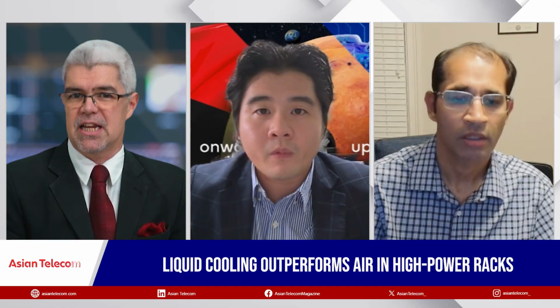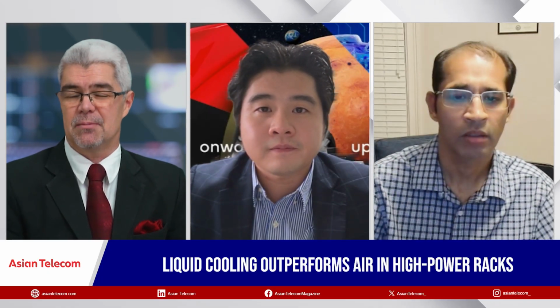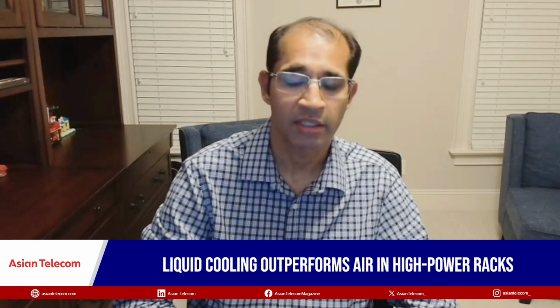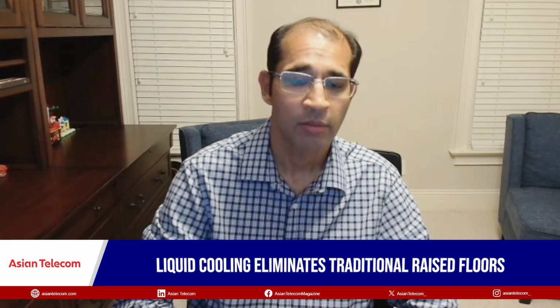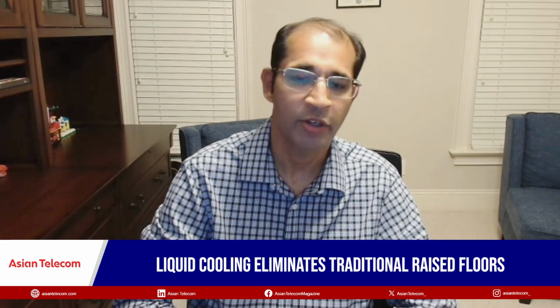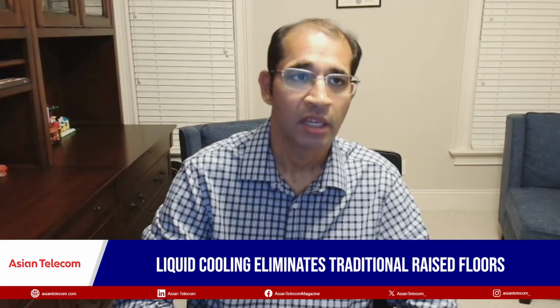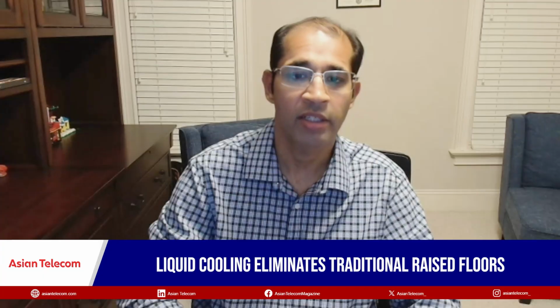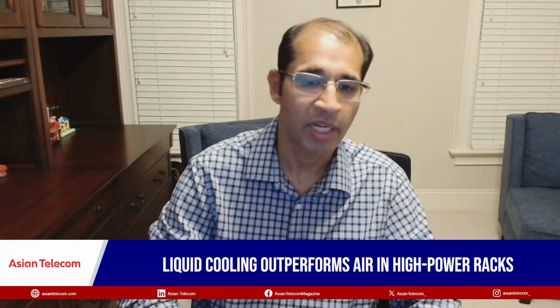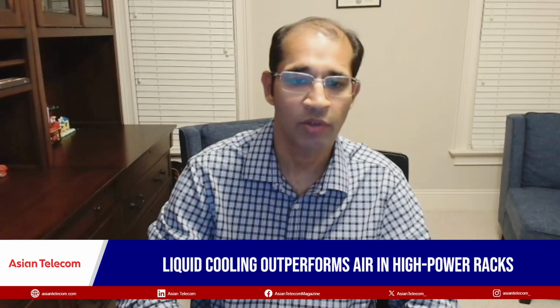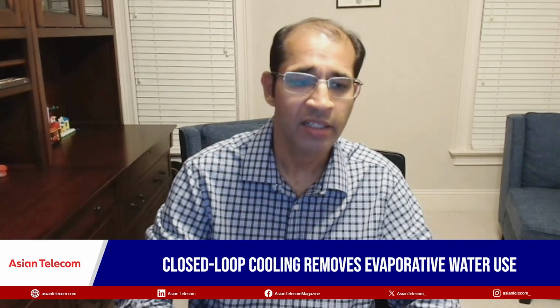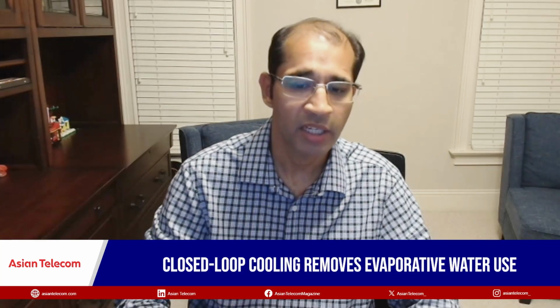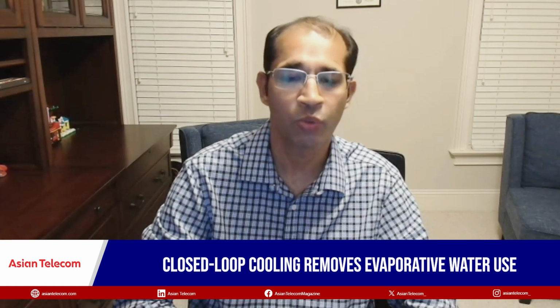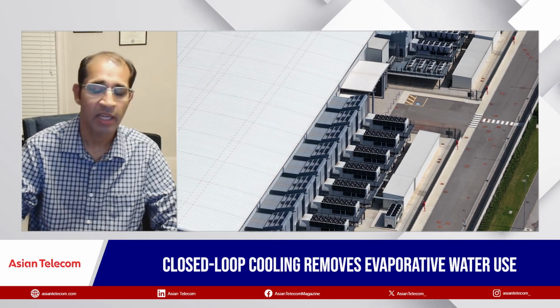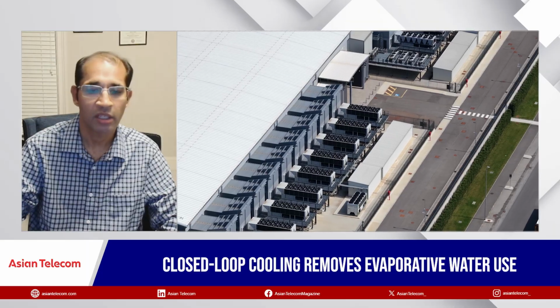What changes will we see in data center design as liquid cooling becomes mainstream? It's a completely new way of looking at data centers. You won't require raised floors any longer, and there will be a lot of new plumbing required to bring water inside the data centers. Liquid cooling, if used in closed loops, can also get rid of the evaporative method of cooling combined with air cooling, which consumes a lot of water. With liquid cooling, the entire IT infrastructure and servers have to be reconfigured and re-optimized, it's a completely new way of design. These buildings will have much better PUE and will reduce electricity use.